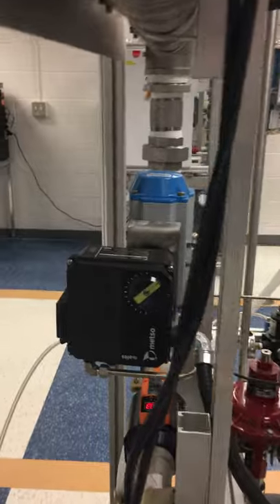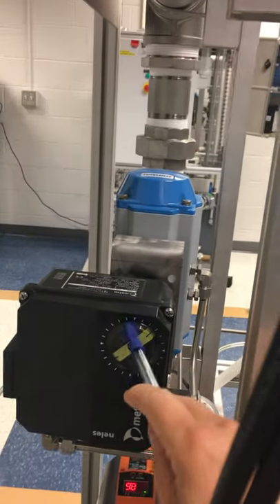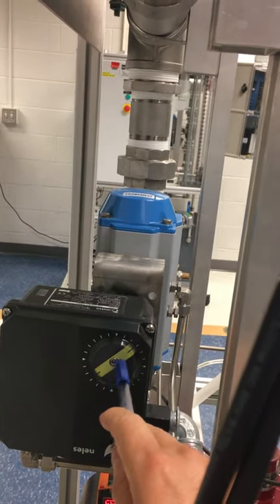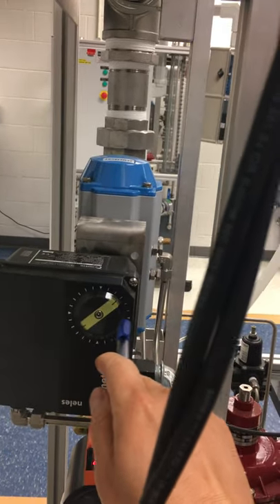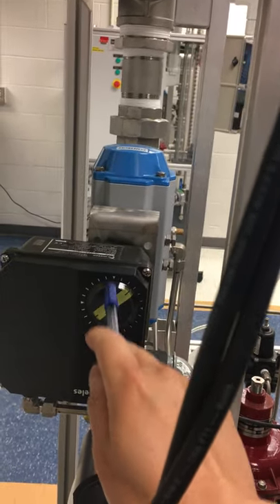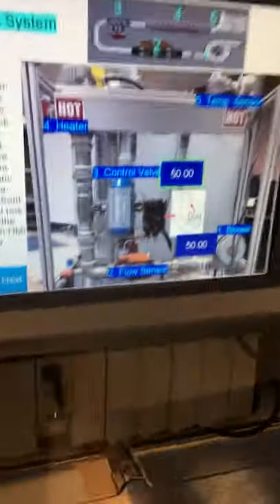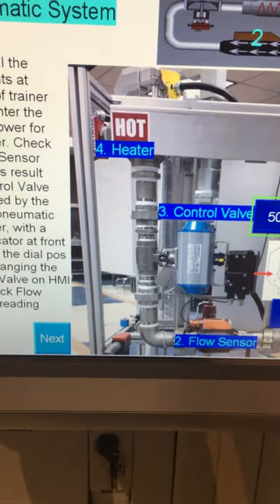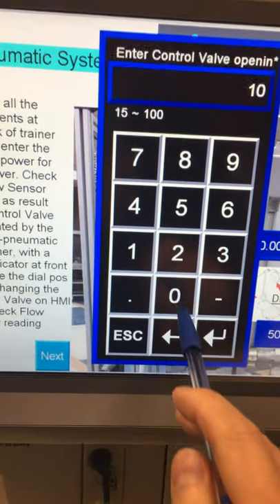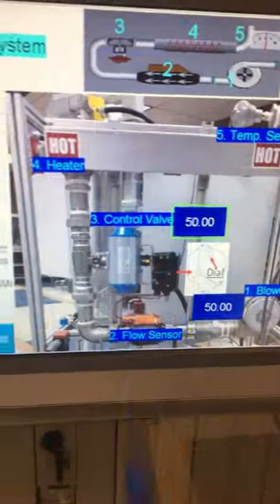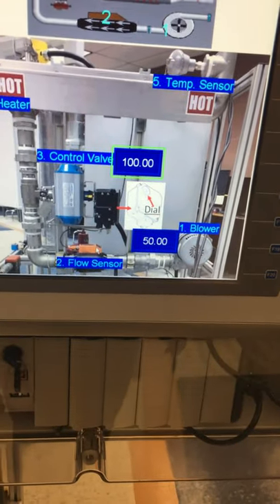You can hear the compressed air, right? It's working. Then I notice here the dial, right? So right now it's on 25 degrees, something like that. Before it was vertical, right? So that indicates from outside, you can see the control position change. Most of the time, maybe we can just make it open to 100%. I'll leave it at 100% on that. So the control valve is totally open.